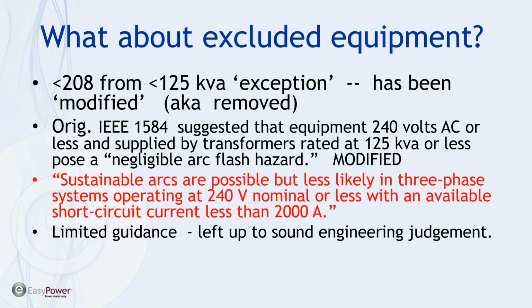The question always comes up about the low voltage exception. And the question was, what about excluded equipment? It used to be, below 240 volts, below 125 kVA supply, the standard says we could ignore those loads as an arc flash hazard. Originally, it suggested that there was less likely of an arc flash at that area, and so frequently that type of equipment was disregarded in terms of doing data collection and included in the model.